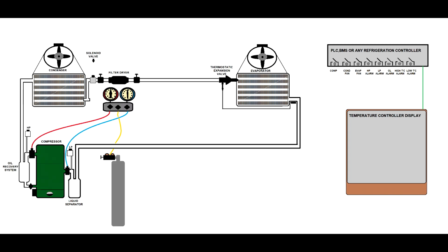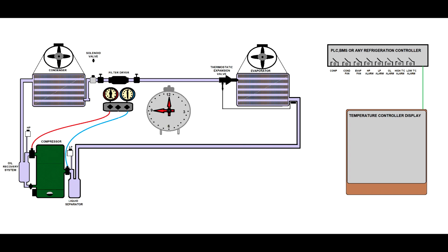So once you build your system, you have to test it. You have to apply pressure to see if you have a leak. So you check all the pipes and then you use a nitrogen tube and apply pressure as per your system specification. So you apply as many bars as required into the installation. You remove the tube because sometimes the valve will let it by and you don't want to have the surprise of overpressurizing your system and destroying it.